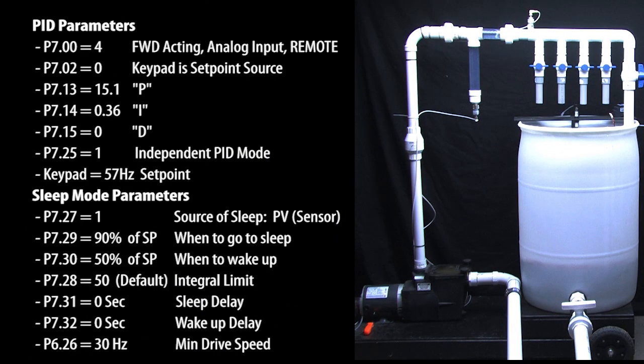To switch from forward to reverse acting, we only need to change these guys. We need to tell PID the sensor signal is reverse acting by setting parameter 7.0 to a 3.